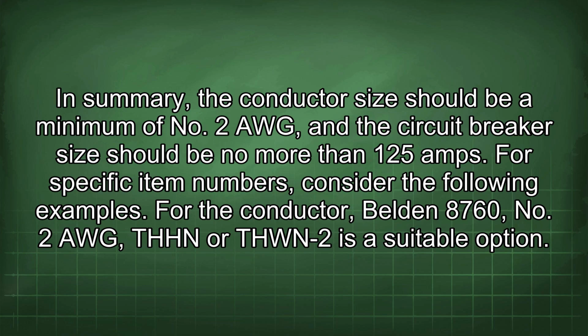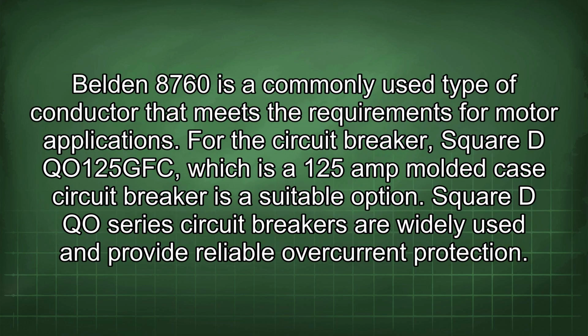For the conductor, Belden 8760, No. 2 AWG, THHN or THWN-2 is a suitable option. Belden 8760 is a commonly used type of conductor that meets the requirements for motor applications. For the circuit breaker, Square D QO 125 GFC, which is a 125 amp molded case circuit breaker, is a suitable option. Square D QO series circuit breakers are widely used and provide reliable overcurrent protection.